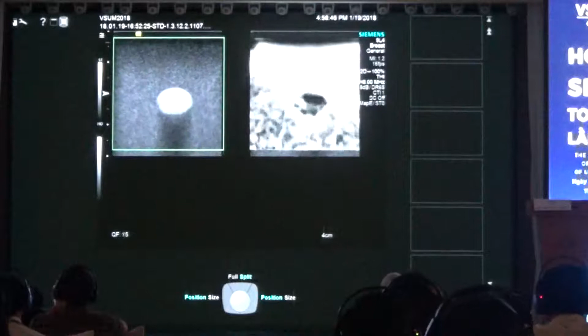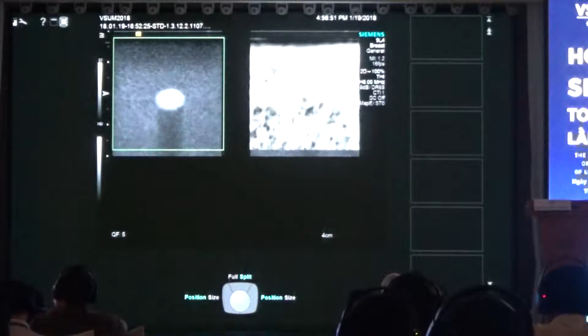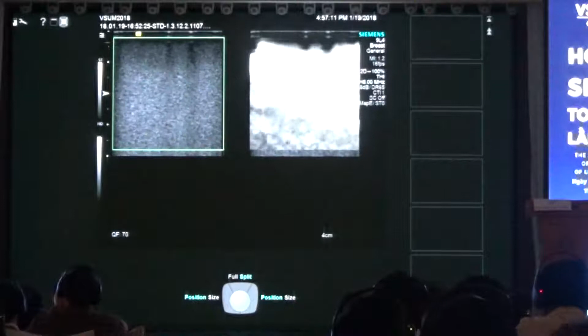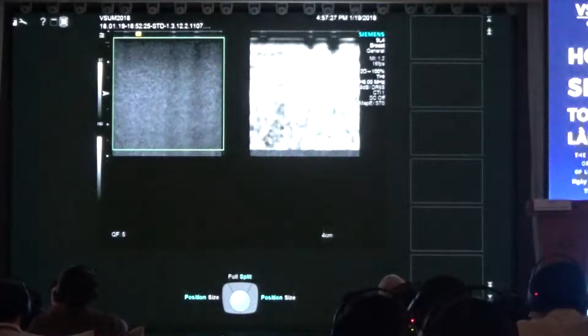Now, one of the things you should look at when you see this pattern, where you tend to have, I call it the worm pattern, it looks like things are changing and it looks like worms moving all over, that's all noise. And you'll often see that when here again what we have is, I have now only got the background tissue. There's only one tissue type. Everything is the same stiffness. So the machine doesn't know what to do because there's no difference. So you often get this noise pattern. And again, if you apply too much pressure, in a real person, it's hard to do in the phantom, you'll get, again, this pattern that looks like flickering white and black areas. That is just noise.